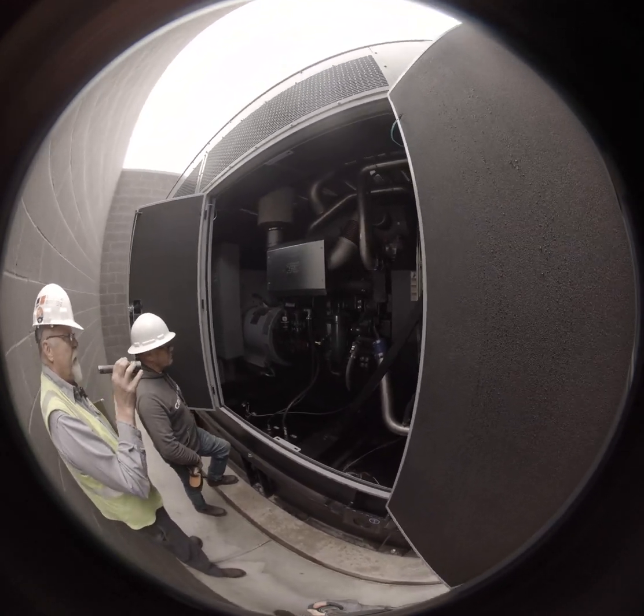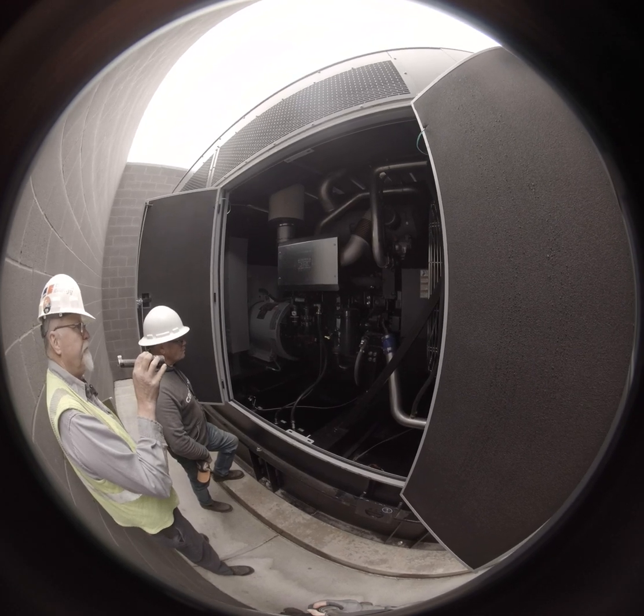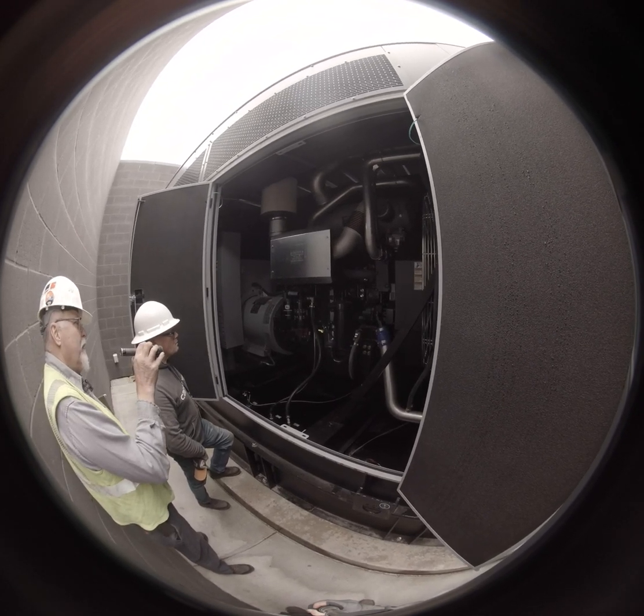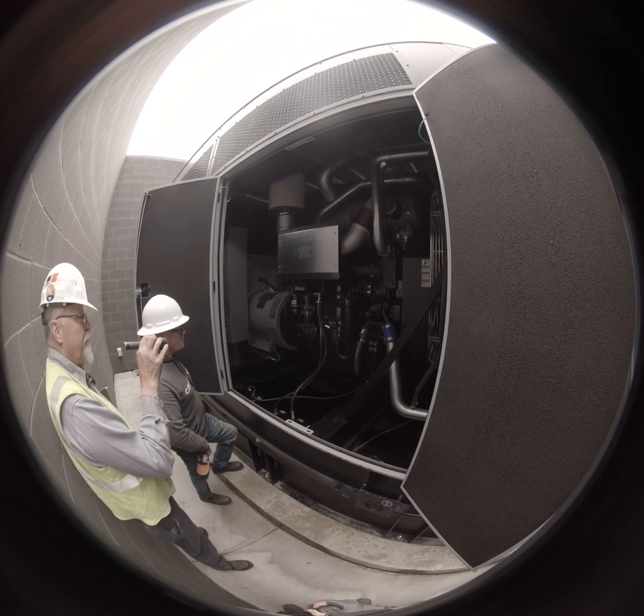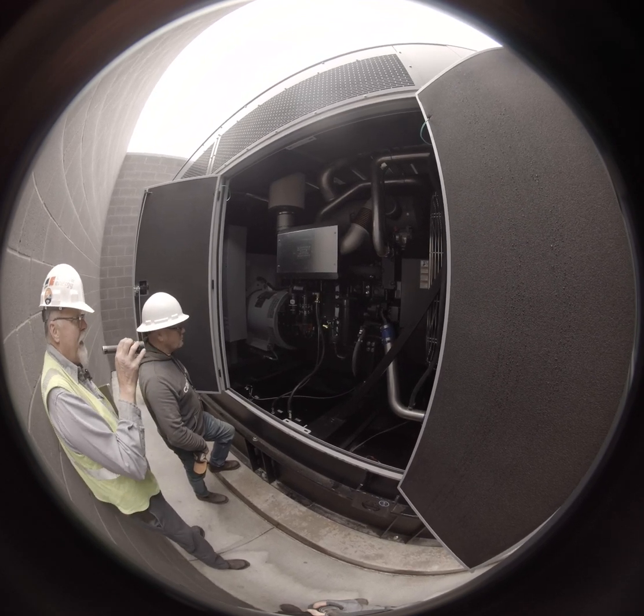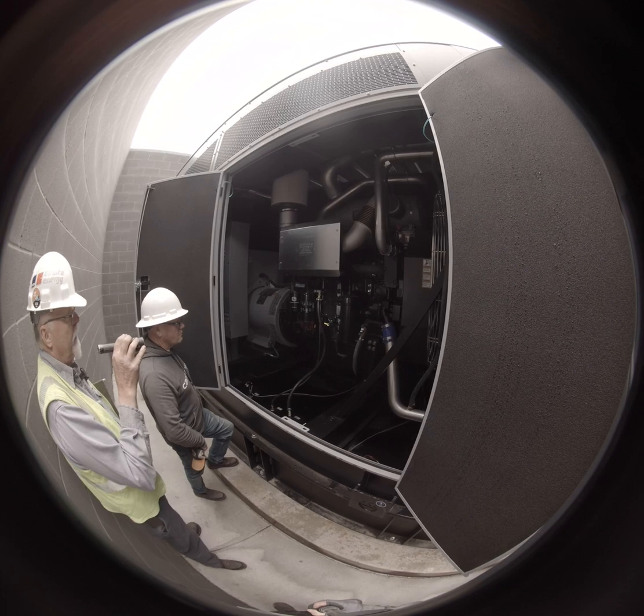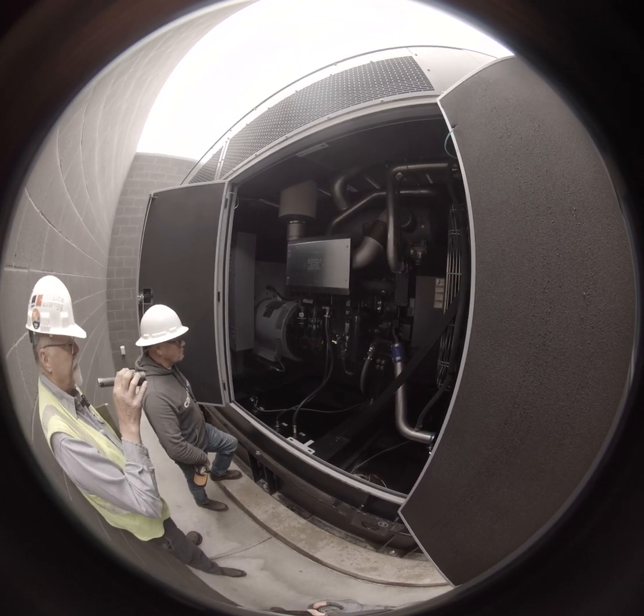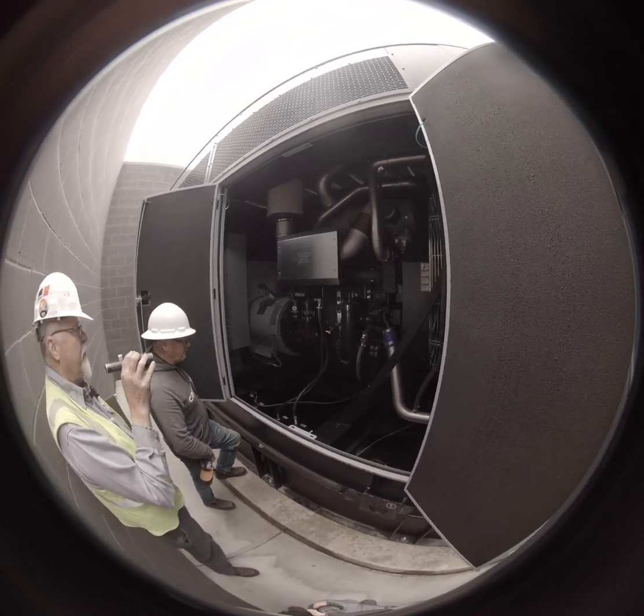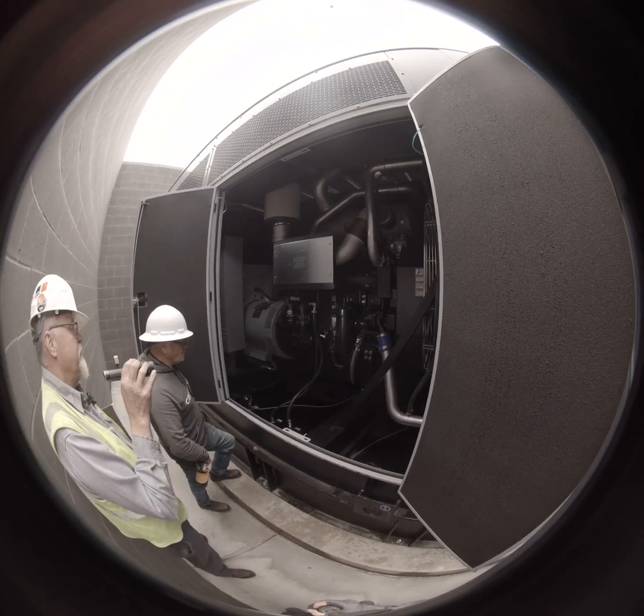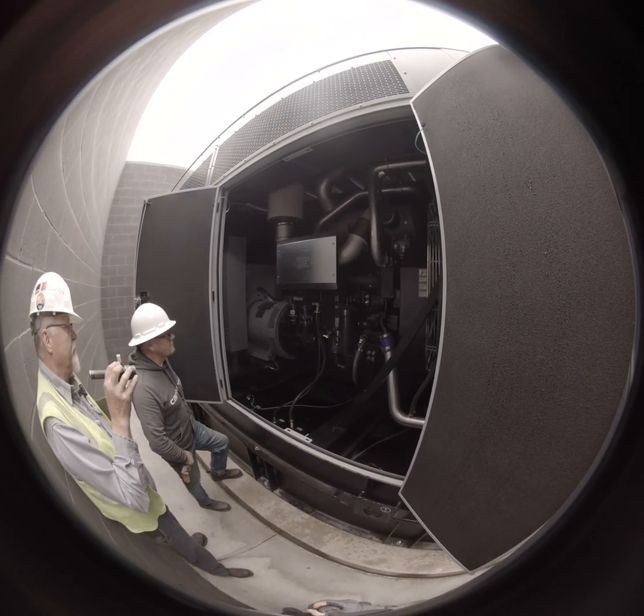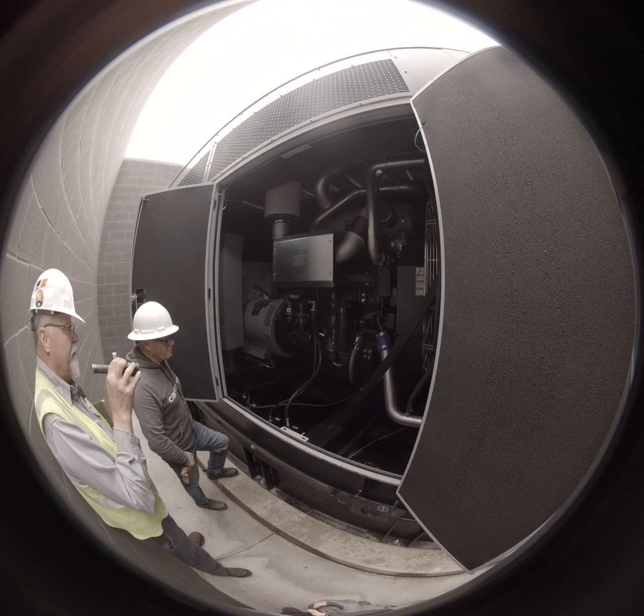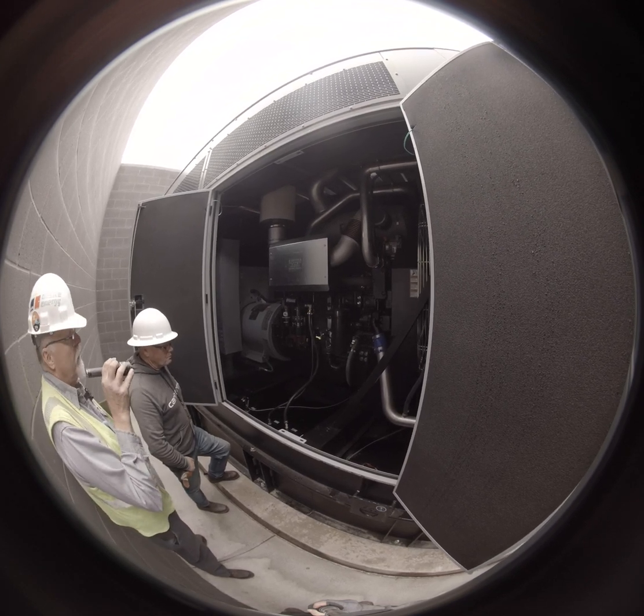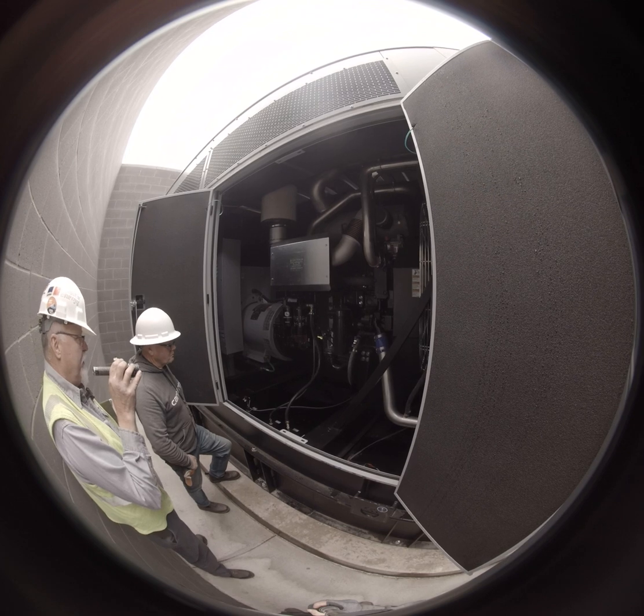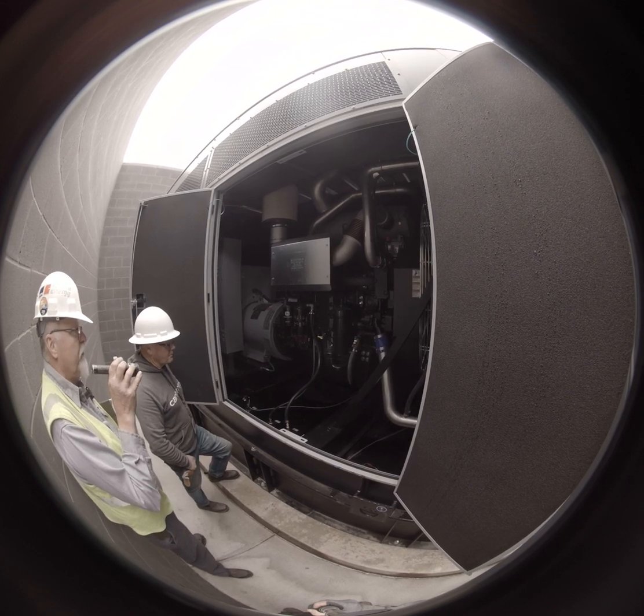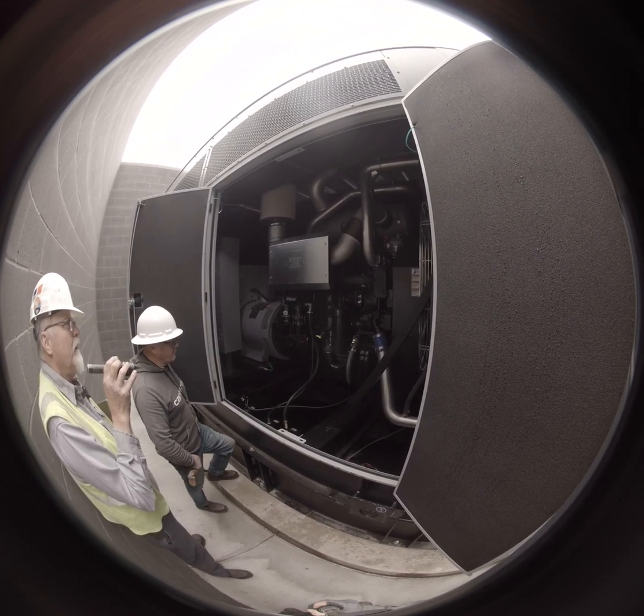So, then we have right here the spin-on oil filter. The yellow guy, of course, is the dipstick. It should be kept at or near the full level at all times. The standard oil on this, it will give you specifications within the O&Ms on it, same as the coolant and all that stuff. But in a nutshell, we run 15W-40 Delo 400 is what our standard is. That's what I know. Yep.